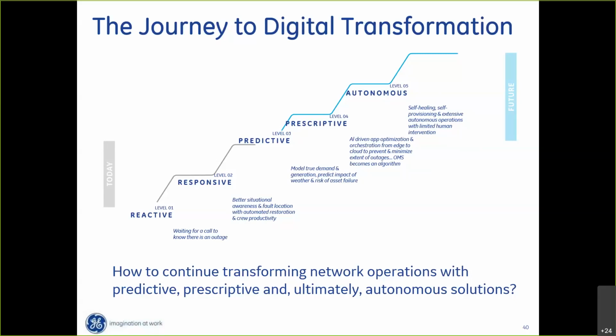Fully automatic, though, is where upstream and downstream restoration is all done automatically, which means the time from the fault occurring to when only the faulted segment has the outage can be less than 2 minutes, 1 to 2 minutes. The reason that's important is that each utility's reliability is judged based on very important reliability indices called SAIDI and SAIFI, right? SAIDI has to do with the duration of the outage, and SAIFI, the F, is the frequency of outages greater than 5 minutes. And if you can have the upstream and downstream customers restored in less than 5 minutes, that's the best possible situation for system reliability. And that's the goal of most utilities today.